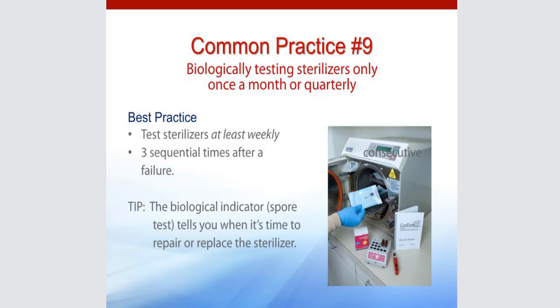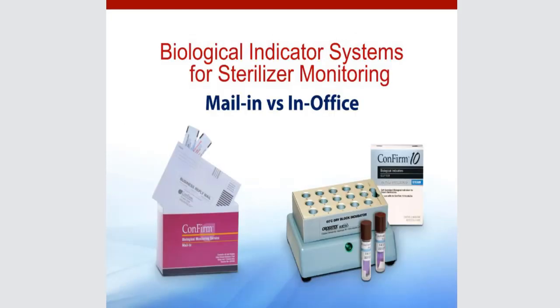Another best practice, while it's not mentioned in the CDC guidelines, using a type 5 indicator when you're using your spore test, you can get immediate feedback from that type 5 integrating indicator. So it's a good idea to pair those 2 items together when you're testing your sterilizer. The type 5 doesn't replace, but it's going to give you that immediate feedback without incubation. You have a choice between mail-in or in-office, whatever works best in your practice, in your hands.